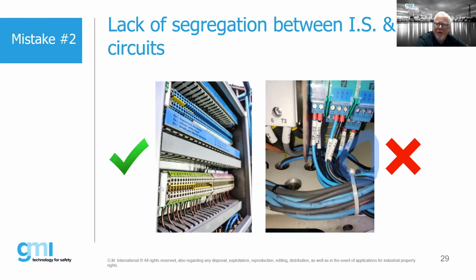Here's an example on the left-hand side where we have our power and our IS separated. We have different duct, we have our IS terminals on the top and our power terminals on the bottom, and we've maintained a separation. Now on the right-hand side, you can see we have some intrinsically safe barriers and a power unit of some sort, I think in this case a contactor. We have a partition located right here. When it came out of the factory, they put a partition to maintain a separation between IS and non-IS, which is certainly allowed.